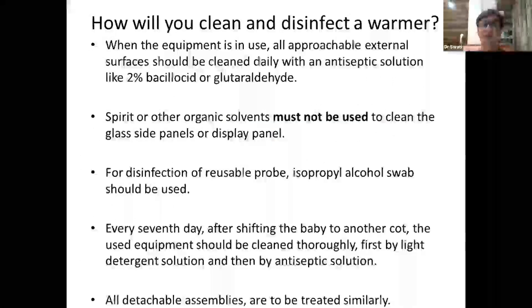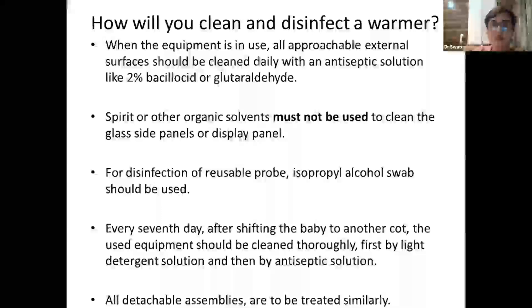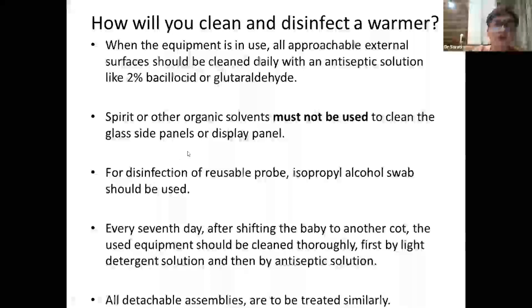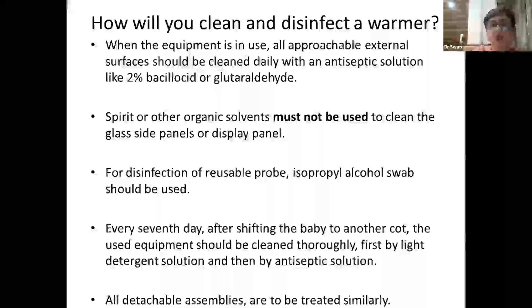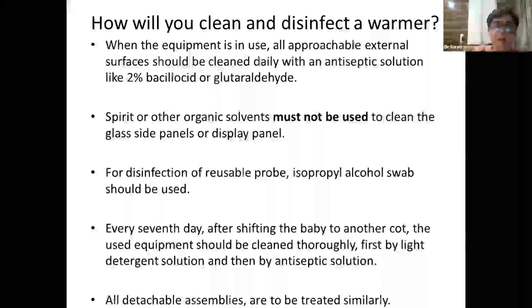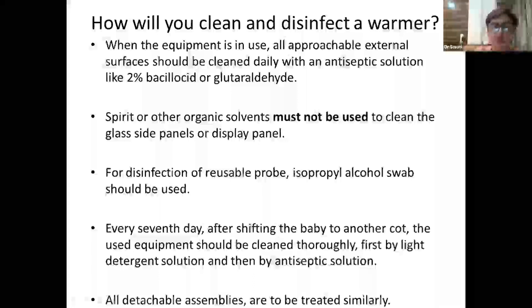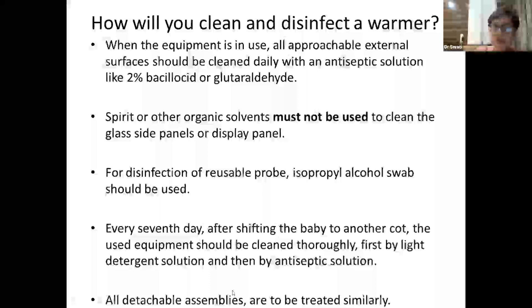For warmer cleaning while a baby is in situ: all approachable external surfaces should be cleaned daily with an antiseptic solution like Bacillocid 2% or 2% glutaraldehyde. Spirit, chlorhexidine, or organic solvents should not be used on glass or display panels as they cause haziness. For the reusable probe, an alcohol swab can be used. Every seventh day, shift the baby to another cot, clean the equipment thoroughly with a light detergent solution followed by antiseptic solution, treating all detachable assemblies similarly.